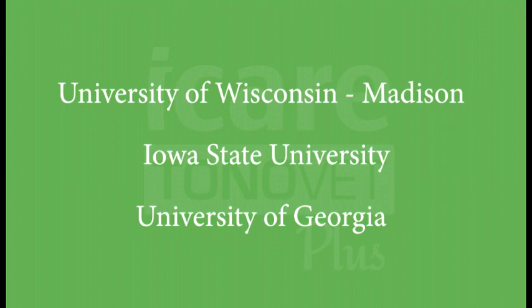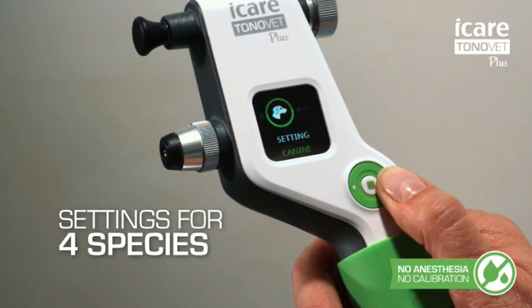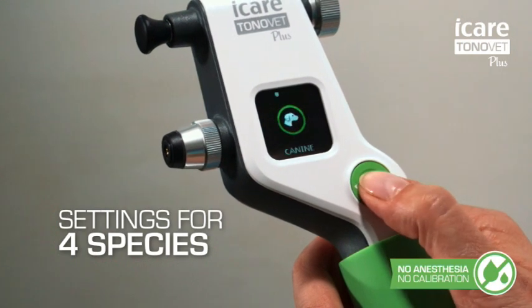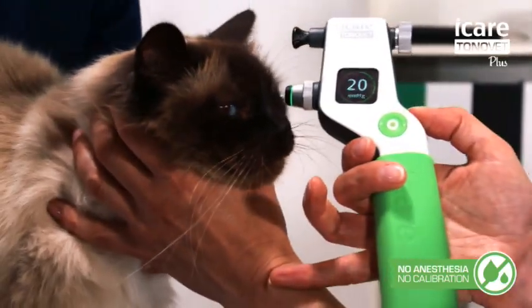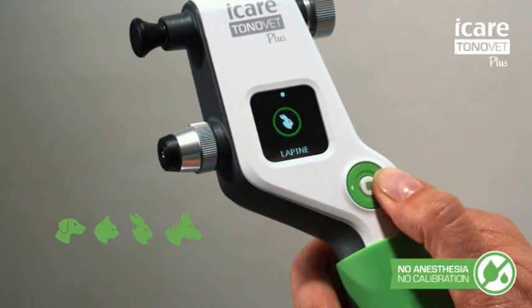The TonoVet is the only tonometer that is calibrated for animals. With the TonoVet Plus, we have improved the accuracy through extensive research with partnering universities. This research combined with software improvements has allowed us to create four settings: one for cats, dogs, rabbits, and horses.